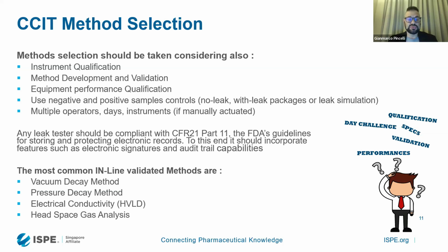As well, we have to take care about the CFR 21 Part 11 compliance, about the electronic signature that should be implemented in all pharmaceutical equipment for production. So take care to verify if that is inside of the machine.